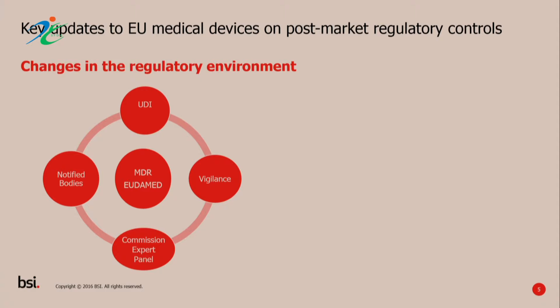UDI, unique device identification. It's defined according to the MDR as a series of numeric or alphanumeric characters that is created through a globally accepted device identification and coding standard. Every device will have company and product details, and it will include the GMDN code, what the product basically is. Some devices will also have to contain product information, batch numbers, etc. Now, you convey the UDI information by using an automatic identification and data capture system. We know this as linear and matrix barcodes. So everything is going to be barcoded, and we'll have all that detail.